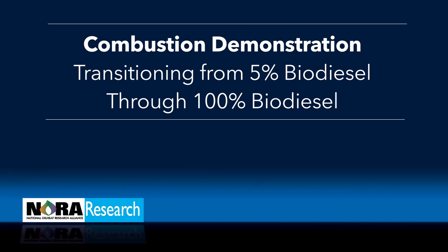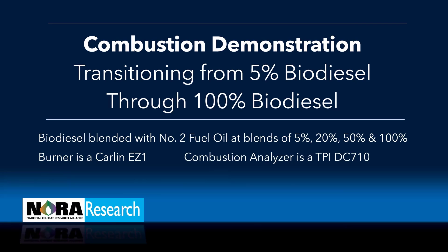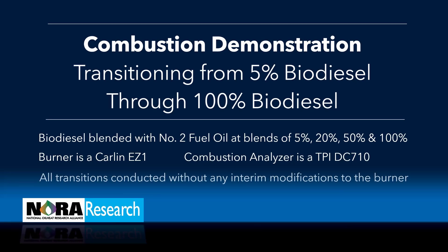Welcome to Nora's combustion demonstration, transitioning from 5% biodiesel through 100% biodiesel. The biodiesel is blended with number two fuel oil at blends of 5%, 20%, 50%, and 100%. The burner is a Carlin EZ1 and the combustion analyzer is a TPI DC 710. All transitions are conducted without any interim modifications to the burner. The burner was set up according to the manufacturer's instructions and smoke was maintained at zero throughout the demonstration.